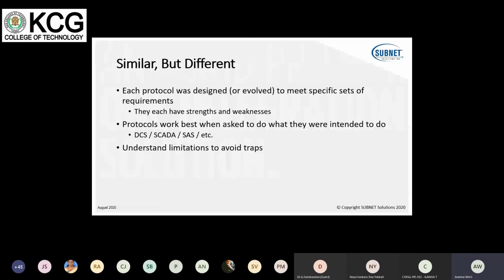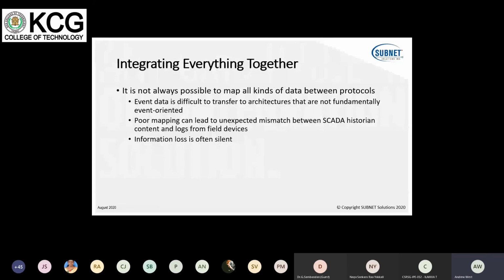One issue I often see with mapping between protocols is that you sometimes lose timestamped event data, and the only time you identify that is when the information in the SCADA historian doesn't match a log extracted from the field device, because something got lost. There's typically no way of identifying that it got lost. It's just a fundamental design mismatch between the way some protocols work. So you can't always get everything just the way you expect, unless you're prepared to introduce extra delays.